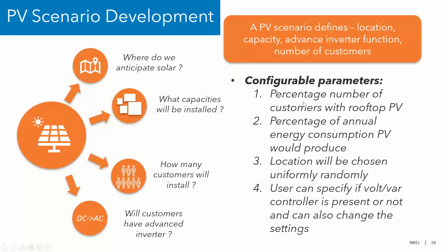If you want to analyze multiple PV systems in the distribution feeder, EMeRGE allows the user to define custom PV scenarios, with four configurable parameters. First, how many customers will have PV, specified as a percentage of customers with rooftop PV. Second, what capacities those PVs will have, defined as the percentage of energy the PV is supposed to generate relative to the customer's total annual energy consumption.